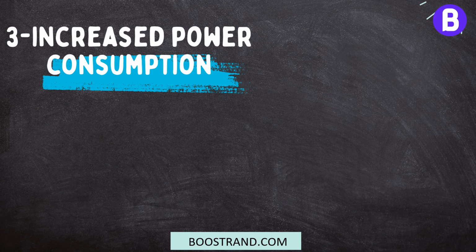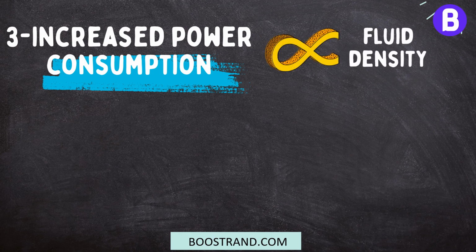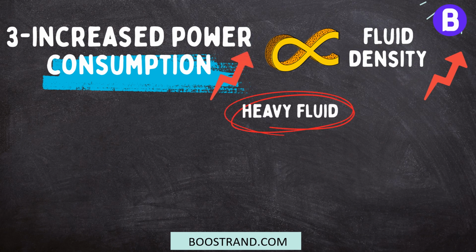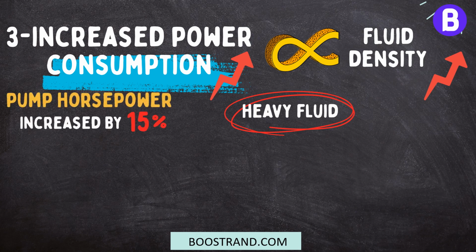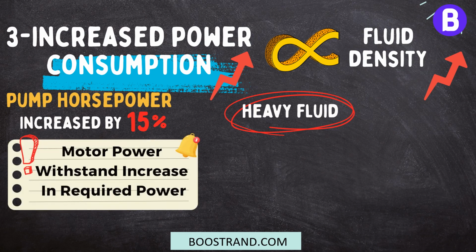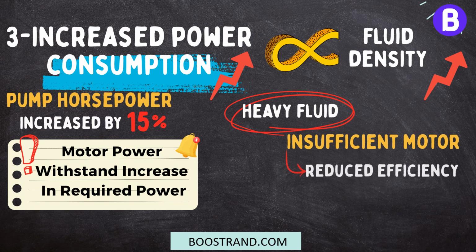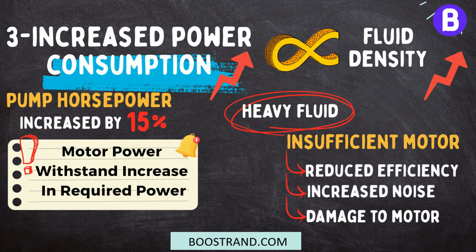The pump's power consumption is directly proportional to the fluid density. When the fluid density increases, the pump's power consumption will increase as well, as we are dealing with a heavier fluid. In your case, the pump horsepower shall increase by 15%. It is important to ensure that the motor power can withstand the increase in required power. If the motor power is insufficient, it can lead to reduced efficiency, increased noise, and damage to the motor.